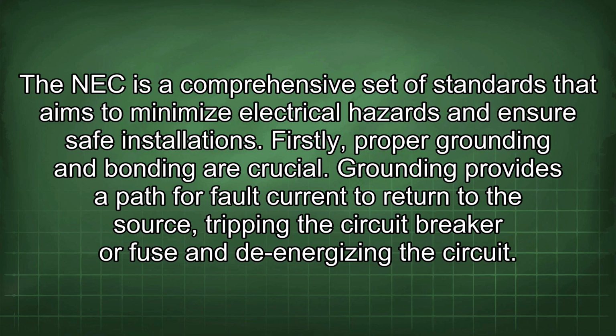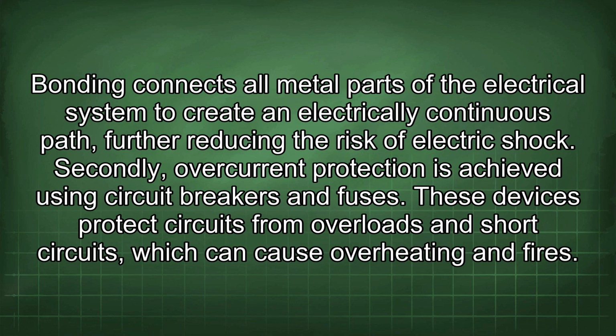Firstly, proper grounding and bonding are crucial. Grounding provides a path for fault current to return to the source, tripping the circuit breaker or fuse and de-energizing the circuit. Bonding connects all metal parts of the electrical system to create an electrically continuous path, further reducing the risk of electric shock. Secondly, overcurrent protection is achieved using circuit breakers and fuses.